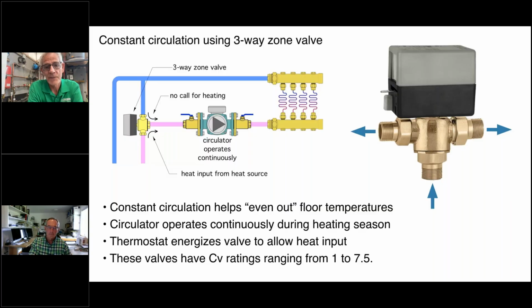So it's a simple thing to do with a three-way zone valve like that. Basically it's always running through the loops, and then when my thermostat calls for more heat, it opens the zone valve, the end switch turns on the boiler, switches the circuit the other way, and now I'm pulling through the boiler. So yeah, we love this application in highway garages where we've got large overhead doors or fire stations.